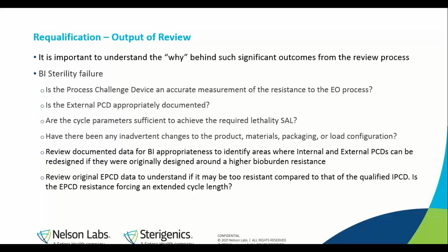It's important to understand the why behind these significant outcomes. So for a BI sterility failure, what you would want to ask is, is the process challenge device an accurate measurement of the resistance to the EO process? Is the external PCD appropriately documented? Are the cycle parameters sufficient to achieve the required SAL?